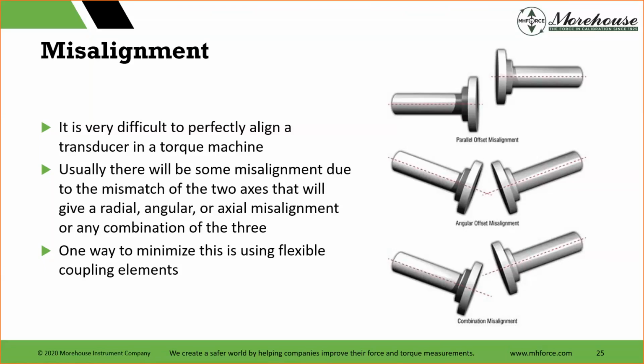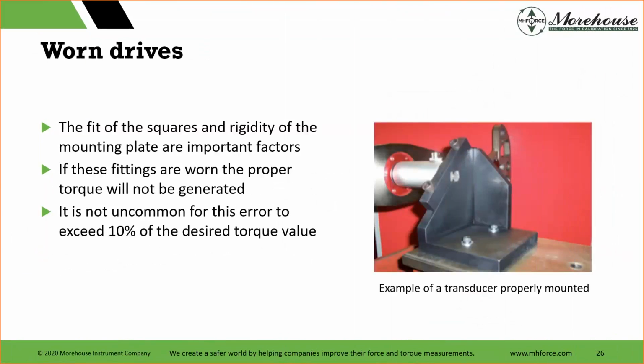But again, it's difficult to align. Usually there's some mismatch of the two axes, and one way to minimize this is using flexible couplings. They get expensive, but until you start doing any of this, I recommend figure out if you have the problem. Do that interlaboratory comparison. Another one, square drives. Square drives are fine, but the fit and rigidity of the mounting plate are important. The more you use a square drive, the more it wears.